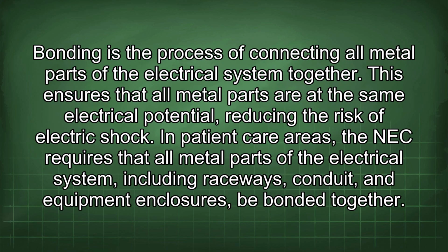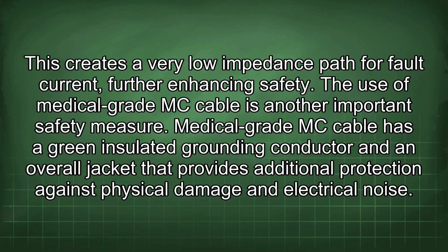Bonding is the process of connecting all metal parts of the electrical system together. This ensures that all metal parts are at the same electrical potential, reducing the risk of electric shock. In patient care areas, the NEC requires that all metal parts of the electrical system, including raceways, conduit, and equipment enclosures, be bonded together. This creates a very low impedance path for fault current, further enhancing safety. The use of medical-grade MC cable is another important safety measure.